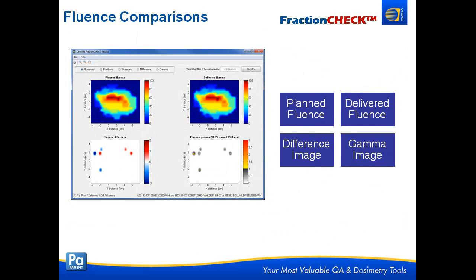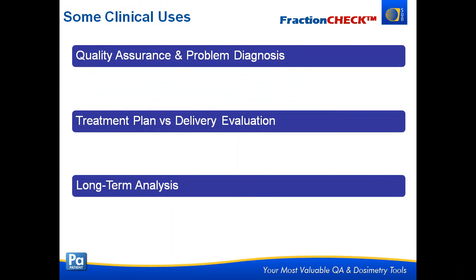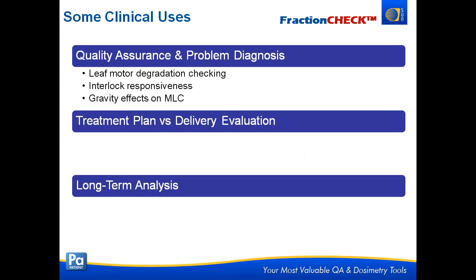The fluence comparisons screen shows the planned and delivered fluences, the difference image, and the gamma image. Adding all that up, what can we actually do in the clinic when we have a tool like FractionCheck? We can do a lot of QA and problem diagnosis — because we have so much information, it's actually a lot easier when we see a problem to figure out what went wrong and how we can fix it.